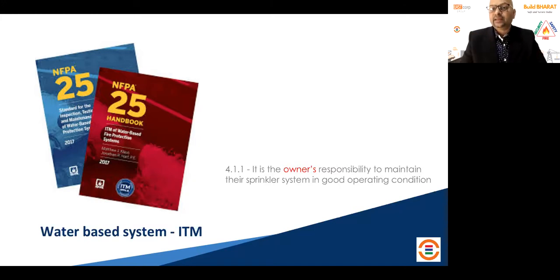Detectors also require a cap during commissioning, only so that they do not come into operation while still under commissioning. But people forget to remove it, and the maintenance team takes the system over as is. The maintenance team does not know what this cap is all about, whether it should be removed or not, and they are happy maintaining the system on record, forgetting about the caps.